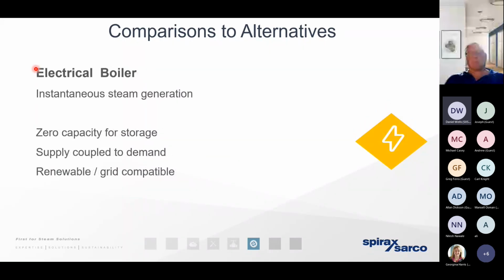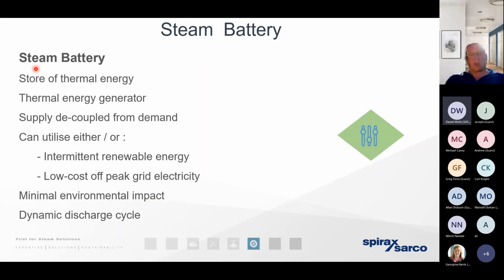An electrical steam generator or an electrical boiler means that because we can only generate that steam, that thermal energy, instantaneously, we can't store it. It means that the infrastructure upstream of the boiler may need to be significantly larger than it is at the minute, because we've got to be capable of ensuring that the supply can satisfy the demand. So that may be a challenge. The steam battery, that thermal store, has a significant benefit because it brings all of those advantages together into one common solution. We can use electrical energy in the form of renewables to generate and then store that thermal energy until such a point that it's required by the process. So we can spend a significant period of time charging the thermal store, only to release that energy at certain parts of the day whenever there may be a particular process requirement.